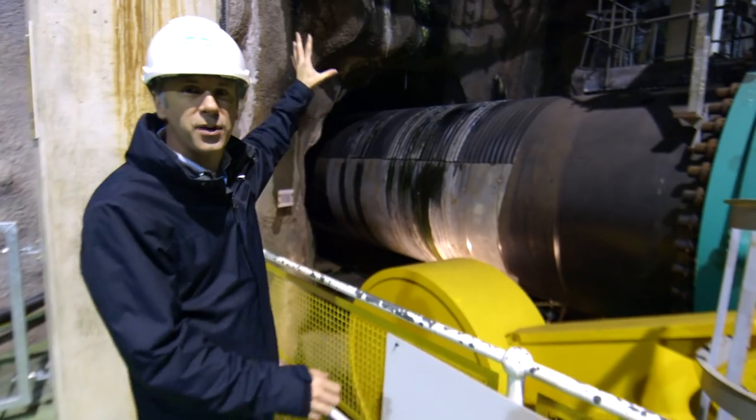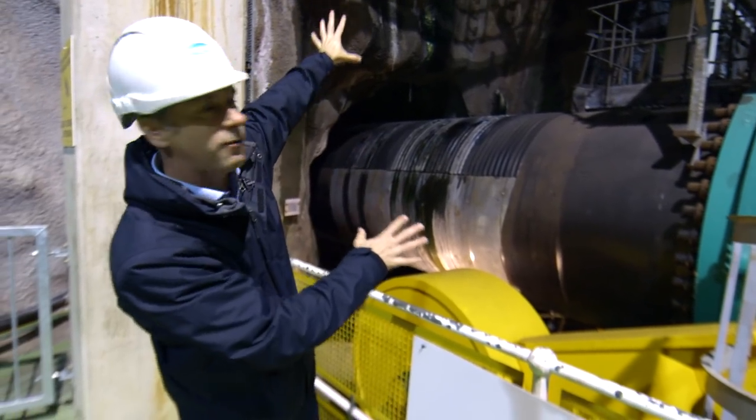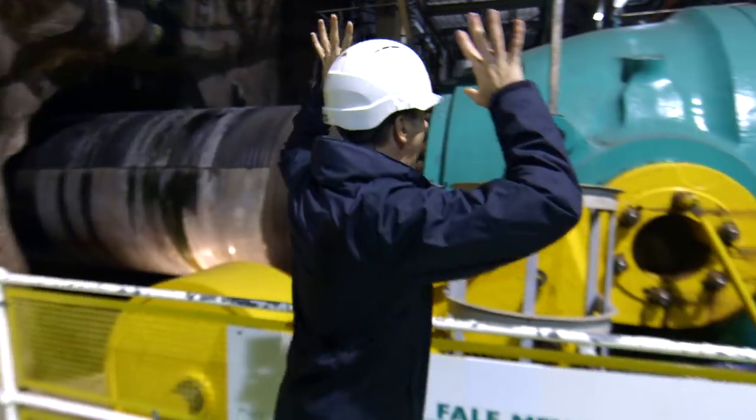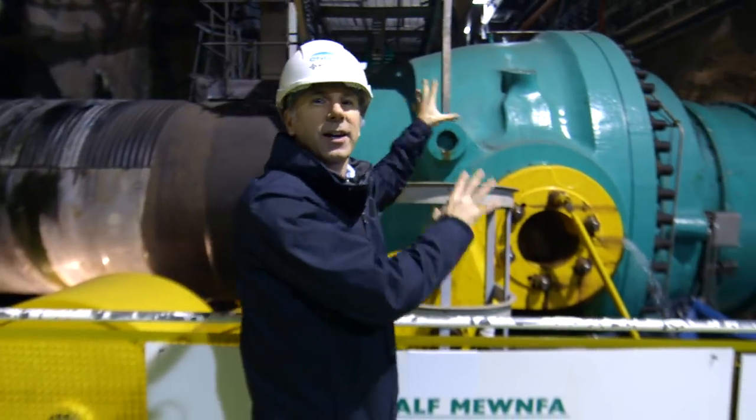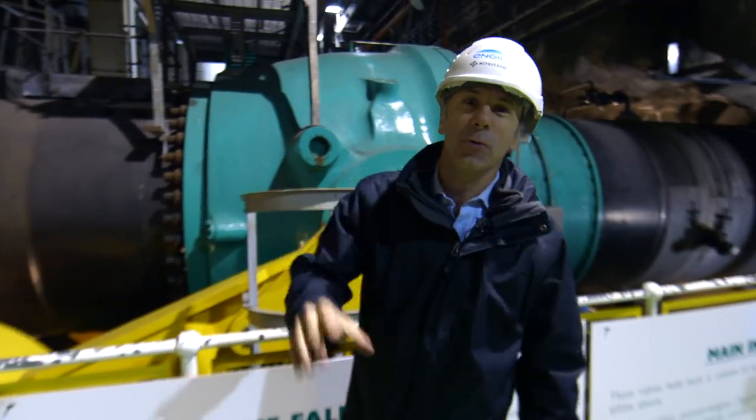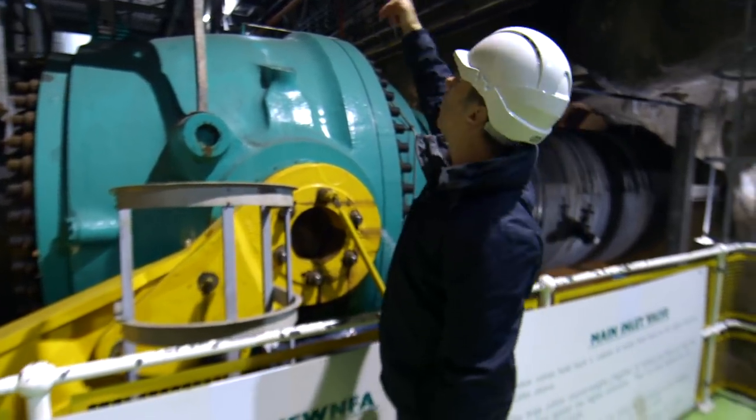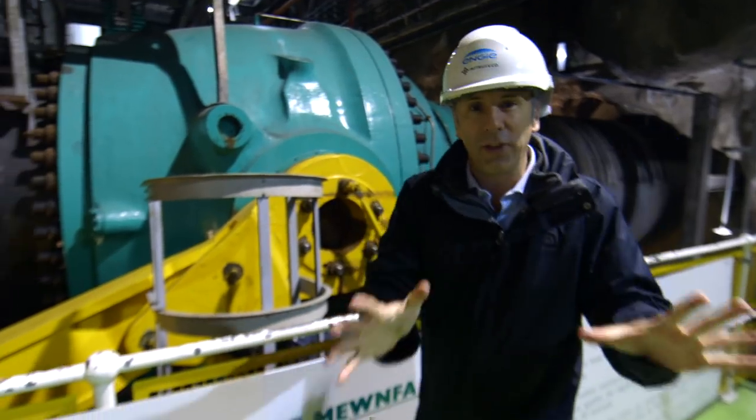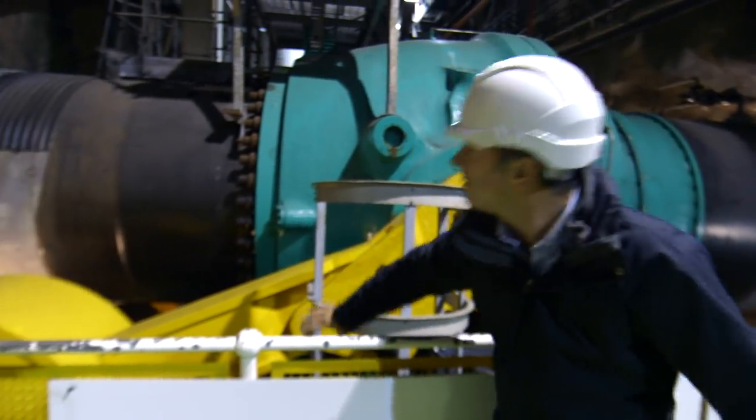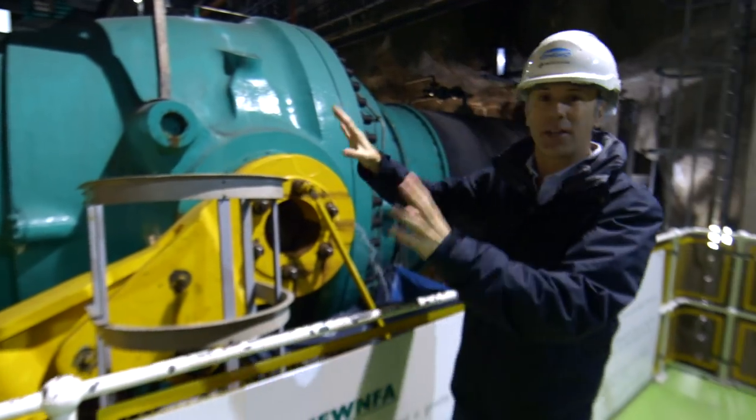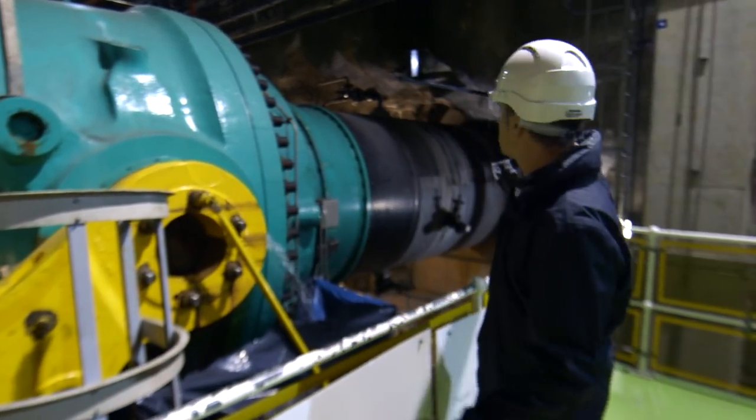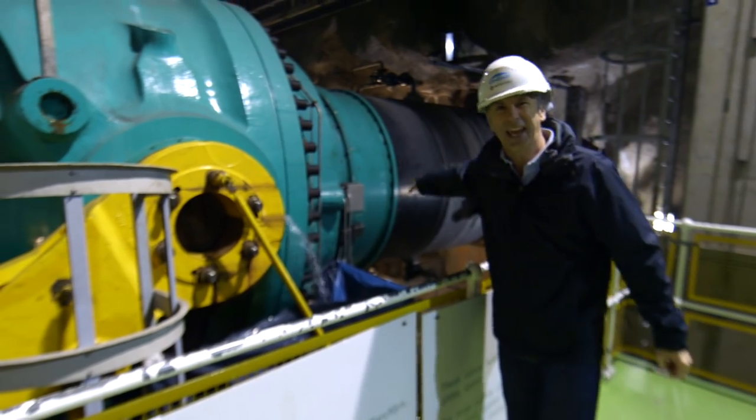Back at Dinorwig, I'm heading deeper underground. The water comes from the lake, which is about 600 meters above us, down this pipe, hits this valve and stops. This is the biggest tap you will ever see. And there are actually six of them all in a row down there. When they need the power, this yellow arm swings up, the valve opens and we get some maximum flow of water through to the turbines through there in about six seconds.